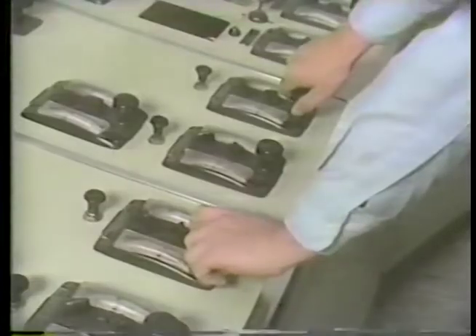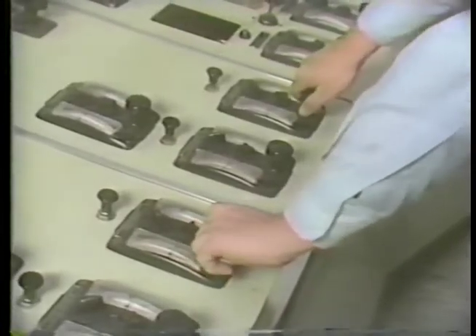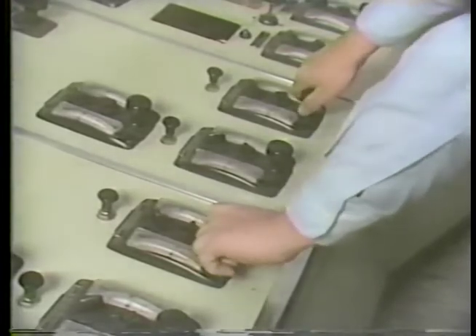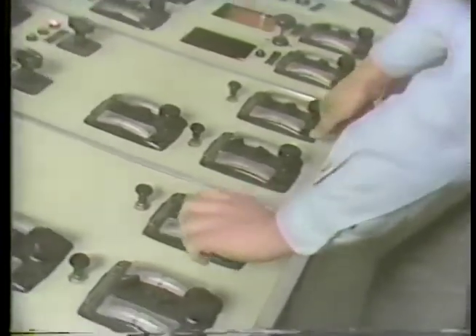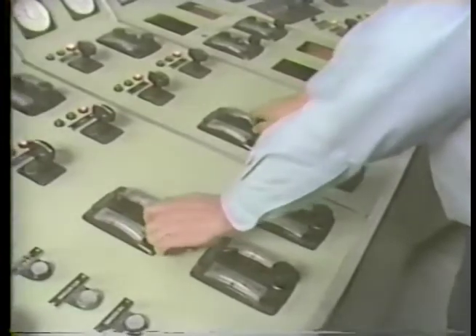As each pulverizer is brought up to speed, the operator checks the boiler flame to make sure that combustion is occurring properly and that all of the burners have ignited. He then makes any necessary adjustments in air and gas flow through the boiler by increasing or decreasing the damper openings on the forced draft fans and induced draft fans.